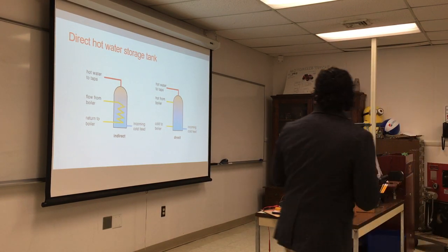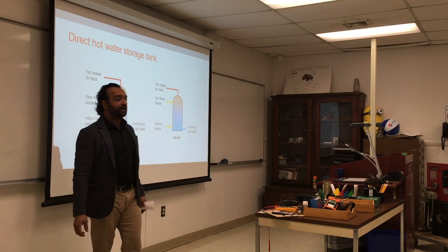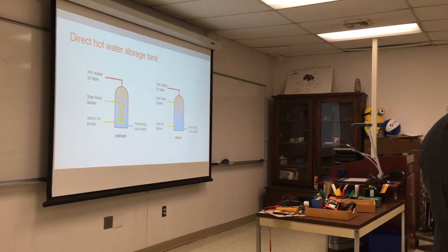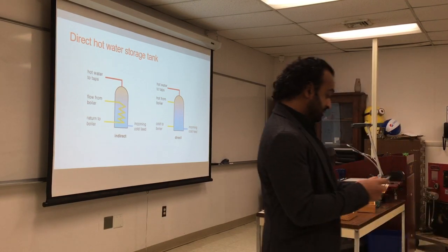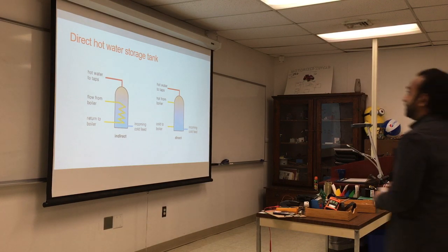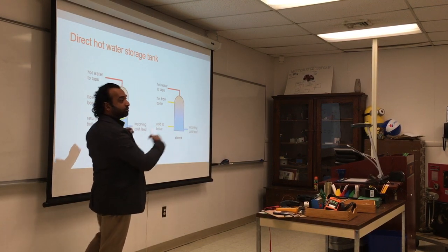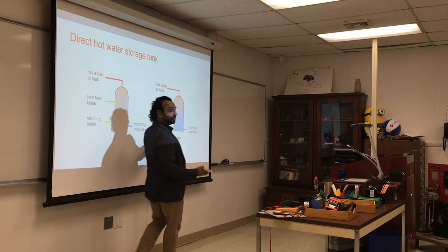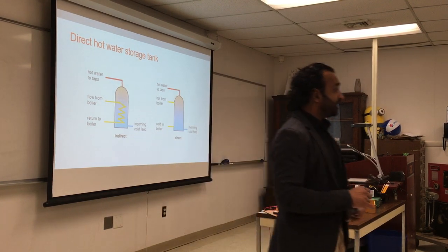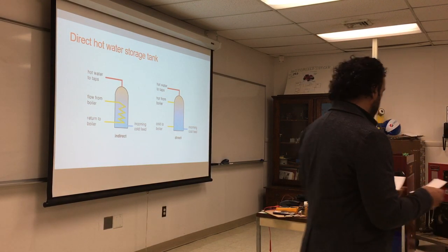What else? What would be some of the advantages of using indirect instead of just using the water in the system and circulating the water? Nathan? Indirect, but the waters are not mixing. You have a coil just like over here, a coil going to the hot water. Separate them. We don't want to mix water and liquid. And what else? You could use antifreeze if you have to. You have cleaner water that does not go through the boiler and get contaminated.